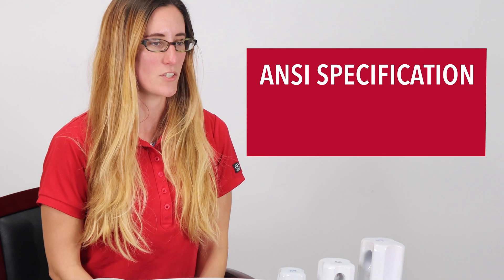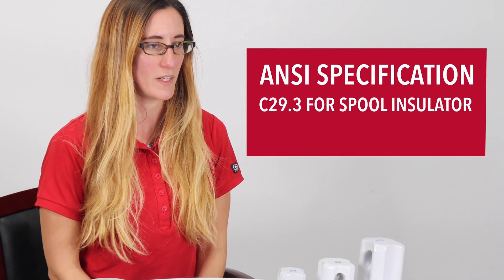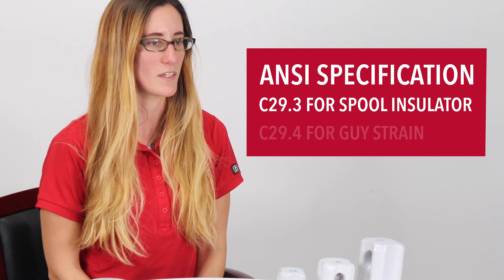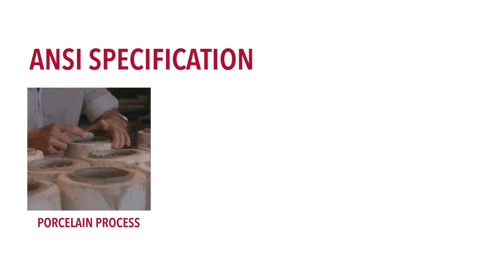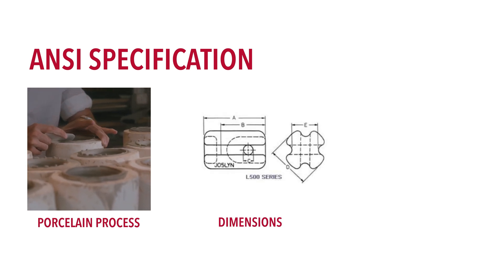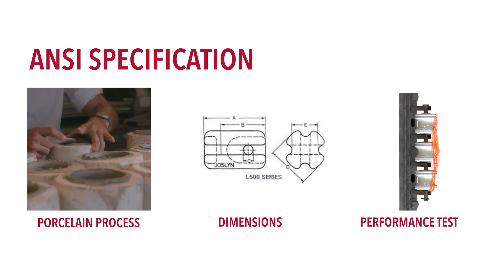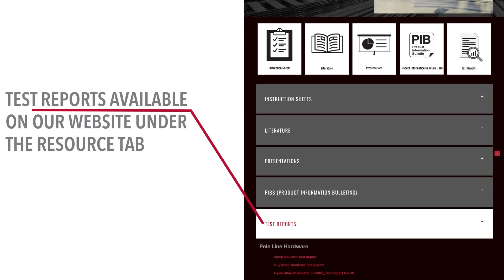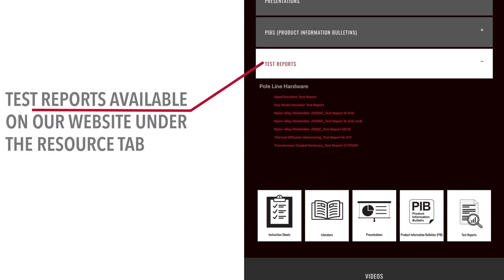The ANSI specification that covers these insulators is C29.3 for spool insulators and C29.4 for the guy strain insulators. This specification covers the process used, which is wet process, the dimensions, and the performance tests they must undergo. This includes strength, visual, dry and wet flashover, and porosity. We have a test report for both insulator types located on our website under the Resources tab.